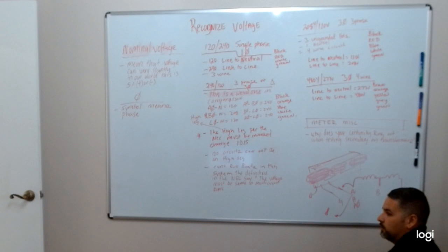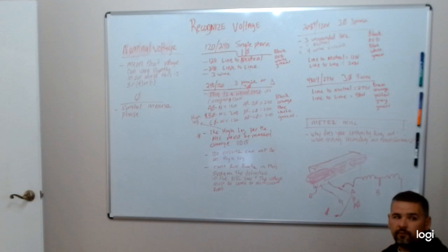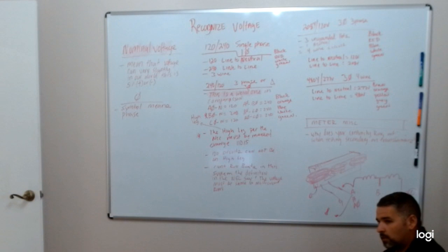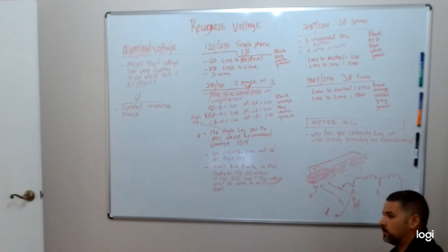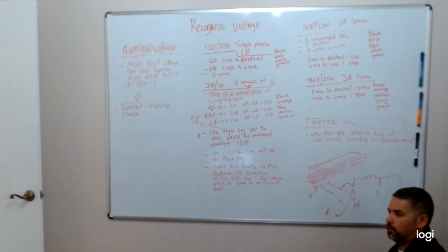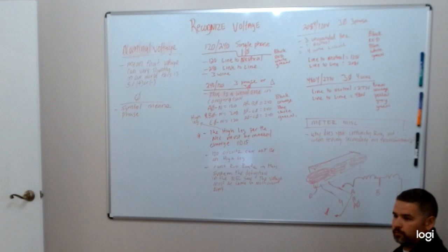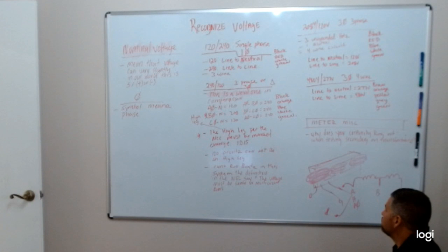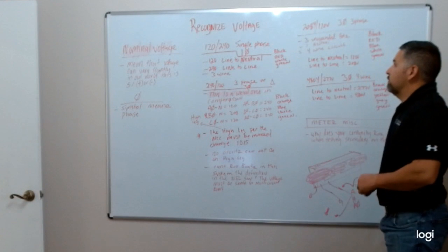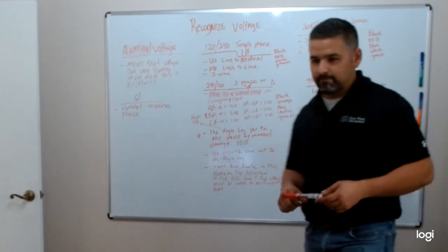So the true way to test it, if you wanted to make sure that there weren't any faults in the system, is to unhook it from the transformer and then do ground to your line on open line, not hooked up to anything, not to any fuses, just point A, point B, see if there's any faults. Okay. And that's what we did at that one project to figure that issue out and why they were messed up. So that is today's little fun fact lesson.